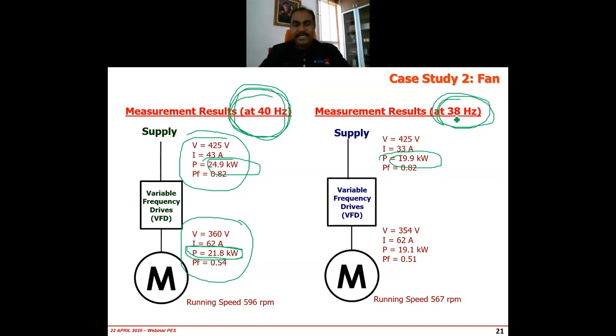That means in this case, there is no additional cost involved because the VFD is already there, the motor is already there. You just have to go there, do some simple settings, and reduce it by 2 hertz. And immediately you see that reduction in the power. And we see that the system works fine. 2 hertz makes no difference in terms of production rate. But in terms of energy saving, there's a huge, significant saving. As I said, it's working 24/7, 365 days.